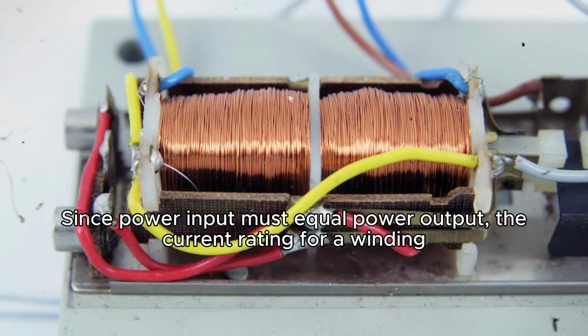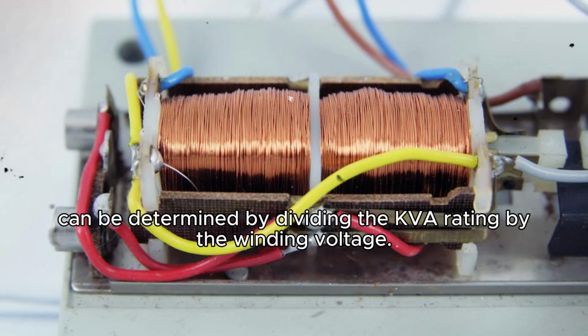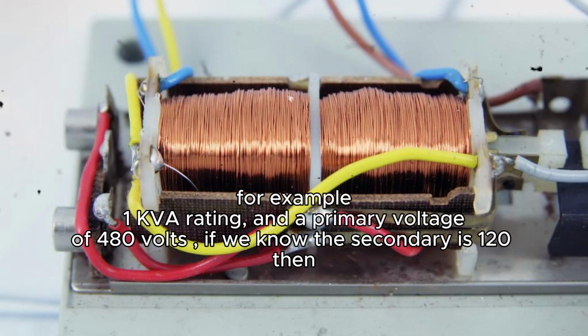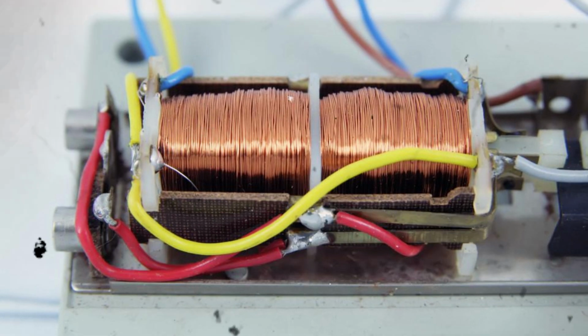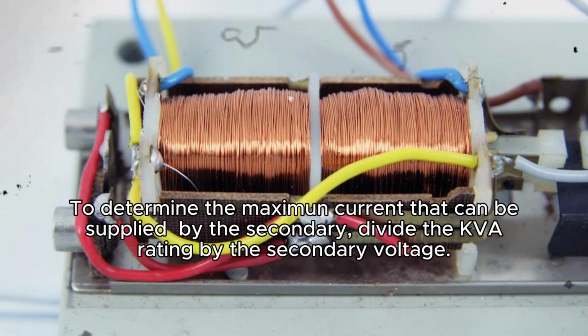Determining maximum current. The nameplate does not list the current rating of the windings. Since power input must equal power output, the current rating for a winding can be determined by dividing the kVA rating by the winding voltage. For example, a 1 kVA rating and a primary voltage of 480 volts. If we know the secondary is 120, then to determine the maximum current that can be supplied by the secondary, divide the kVA rating by the secondary voltage.